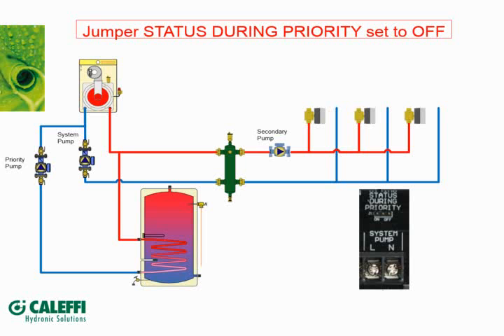All right, I think that's good on the questions. Thanks. So I mentioned the status during priority jumper, just a close-up of this. The status during priority refers to the system pump. So when would you want it off? Let's say we had a system like this, and these are just crude schematics to show the concept, but let's say you had some zone valves, a secondary pump, a hydro separator, and a Modcon boiler with an indirect. So there's a priority call, right? In this case, and granted, you could have the boiler potentially control the pumps, but if our control is controlling the pumps, you would want to fire the priority pump, but you would not want the system pump to run. So in this case, the status during priority would be off.